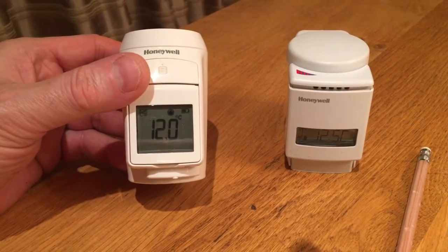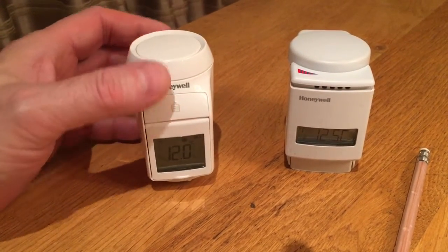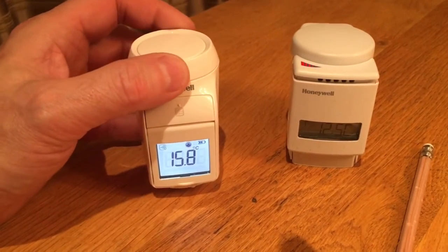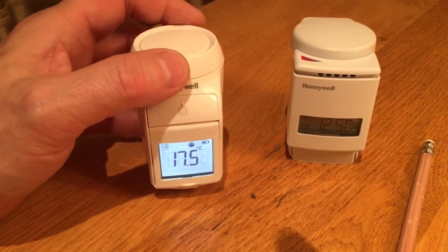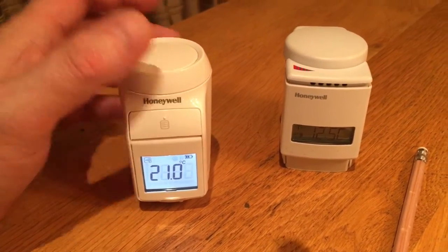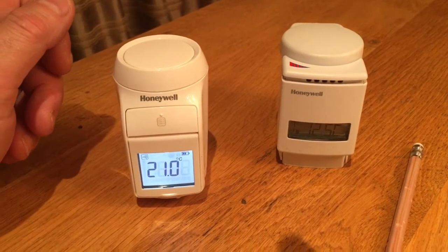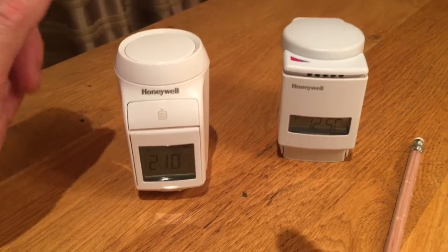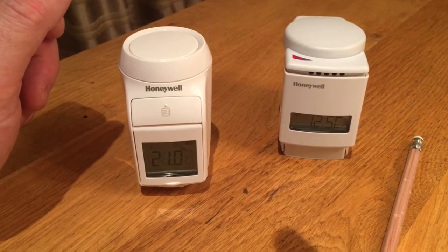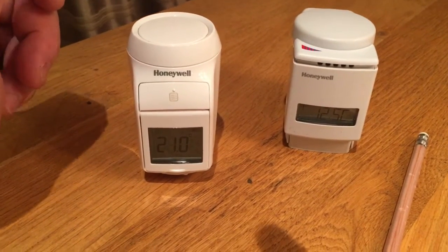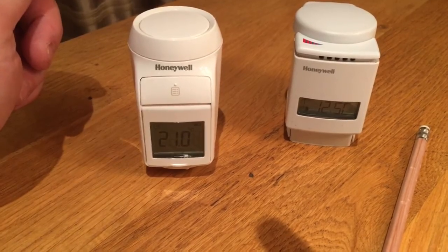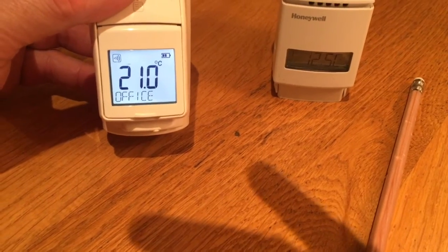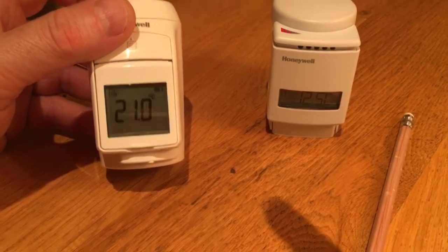Now, it's perfectly possible to go up to this radiator valve and alter that temperature. So for instance, if you were going to go in the room and you wanted it to be warmer, you could just turn it up to say 21. And if you did that, on your Evohome base unit, the target temperature on the display would start to show 21 degrees. However, when you go back to the schedule on your Evohome, you'll find that at the next time zone that you wrote in your schedule, whatever you dialed in on the front of this radiator valve would be overridden by the next time zone on the schedule.